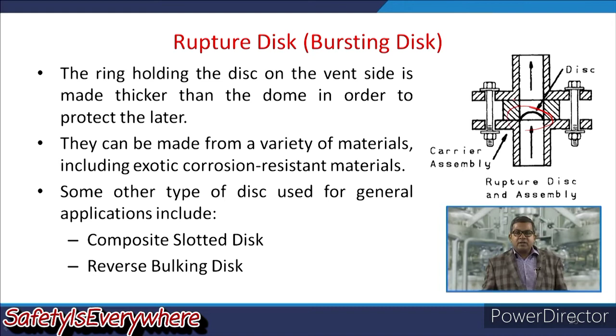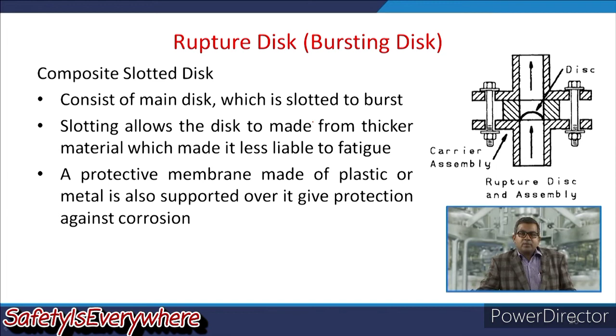Some other types of disc used for general application include the composite slotted disc and the reverse buckling disc. Now let us have a brief discussion about the composite slotted disc. This consists of a main disc which is slotted to burst. Slotting allows the disc to be made from thicker material, which makes it less liable to fatigue. A protective membrane made of plastic or polymer or metal is also supported over it to give protection against corrosion.